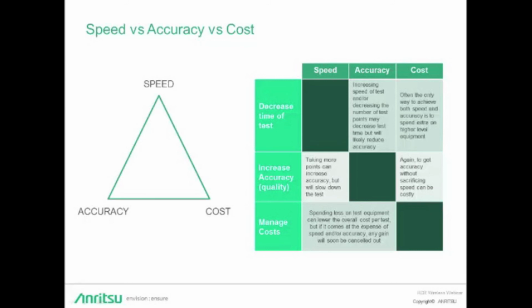Conversely, when you want to increase accuracy, which again is pretty much the same as quality, you're either going to have to slow down your test system or take more points, or spend more time and more money on higher-end equipment. Now, at the bottom of our plot here, if managing costs is your priority, that may have to come at the expense of speed or accuracy or both. So with that understanding, let's talk about the factors that most affect measurement speed of power meters and sensors.